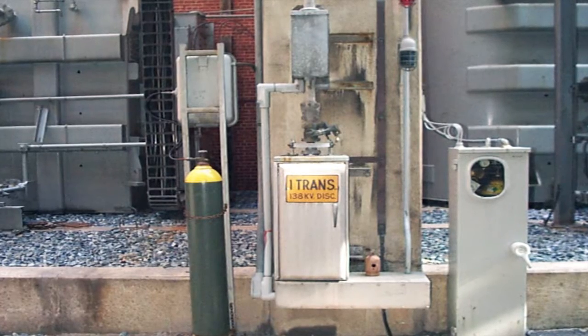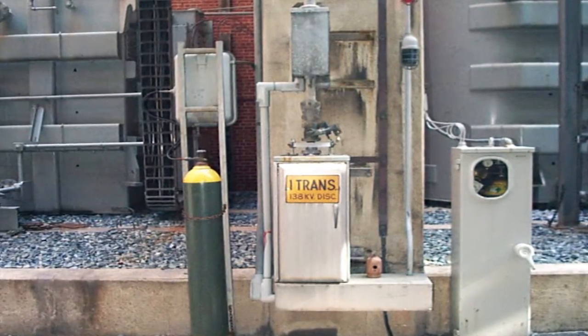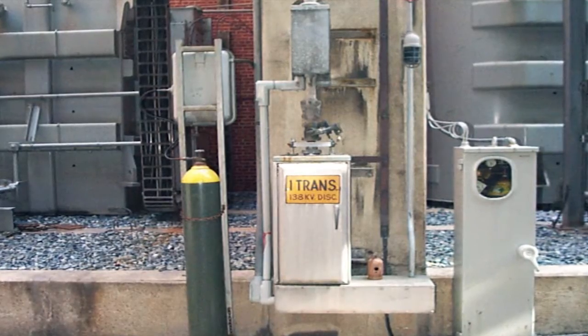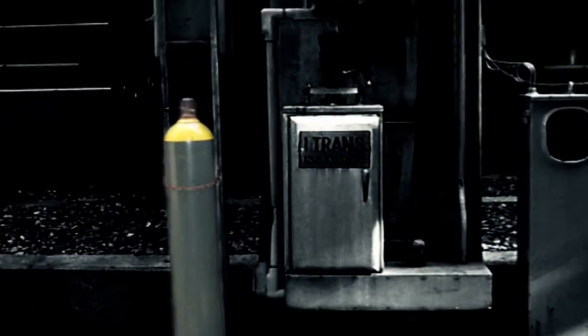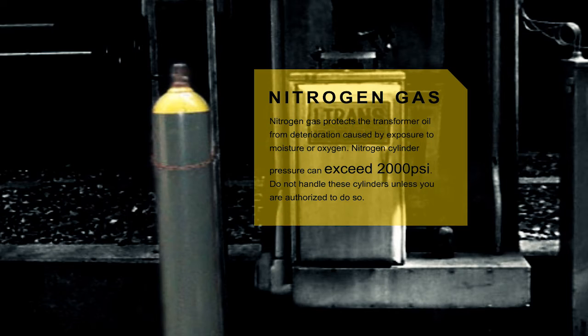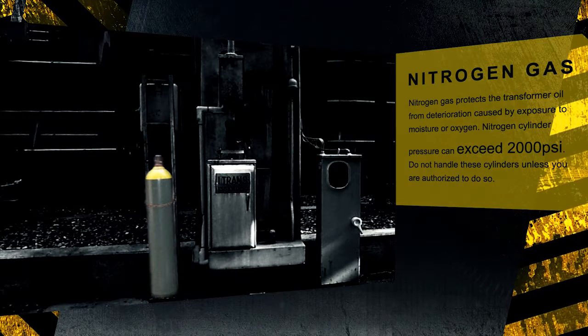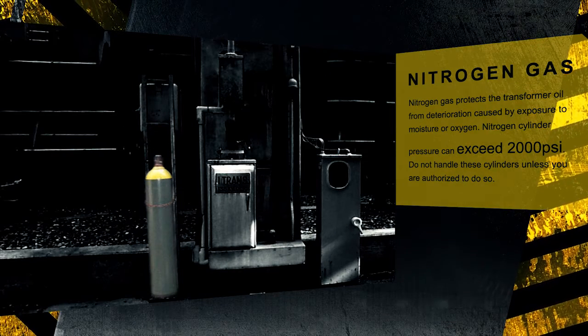Nitrogen gas protects the transformer oil from deterioration caused by exposure to moisture or oxygen. Nitrogen cylinder pressure can exceed 2,000 psi. Do not handle these cylinders unless you are authorized to do so.